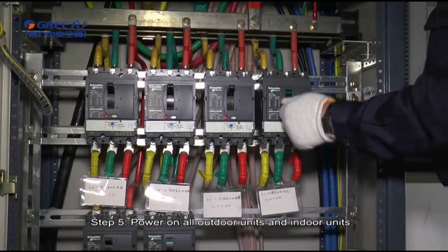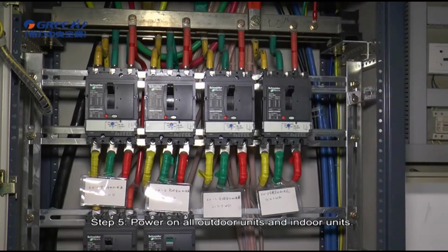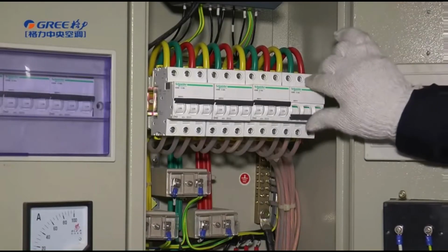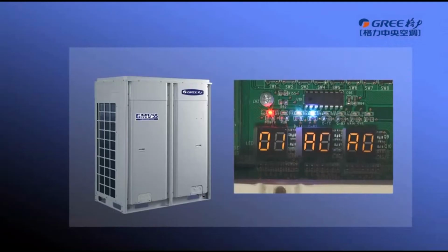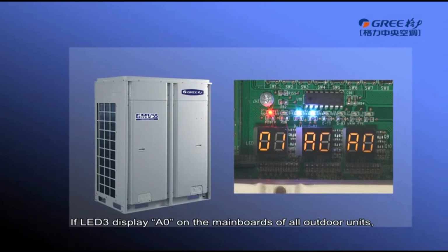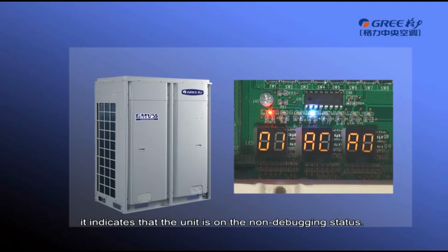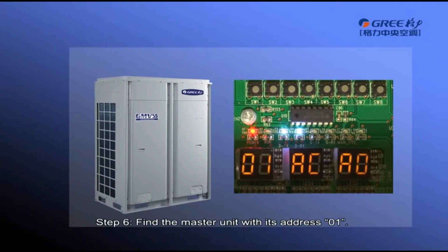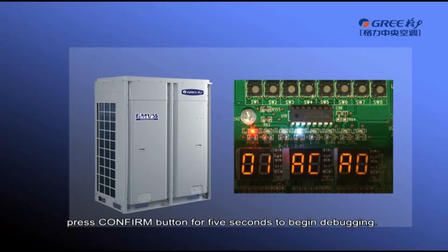Power on all outdoor units and indoor units. If LED displays A0 on the main boards of all outdoor units, it indicates that the unit is in non-debugging status. Find the master unit with its address of 01 on the master unit. Press the confirm button for 5 seconds to begin debugging.